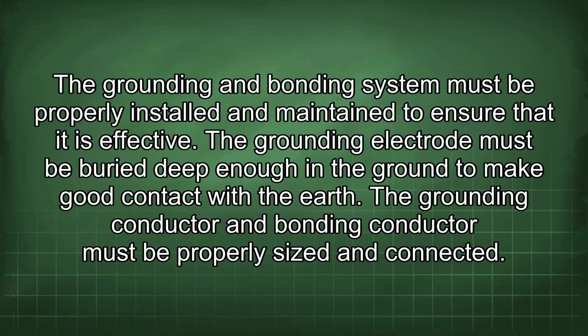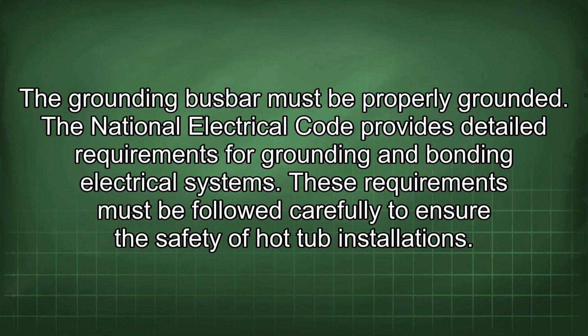The grounding and bonding system must be properly installed and maintained to ensure that it is effective. The grounding electrode must be buried deep enough in the ground to make good contact with the earth. The grounding conductor and bonding conductor must be properly sized and connected. The grounding bus bar must be properly grounded. The National Electrical Code provides detailed requirements for grounding and bonding electrical systems. These requirements must be followed carefully to ensure the safety of hot tub installations.